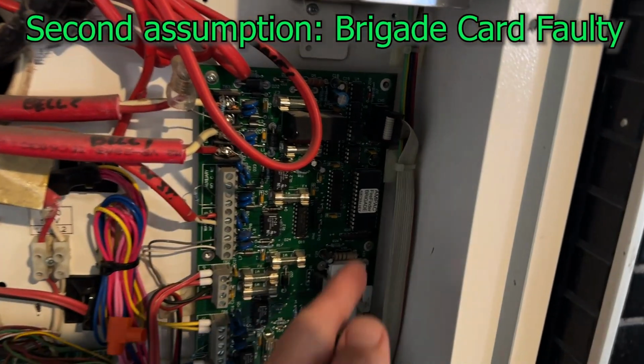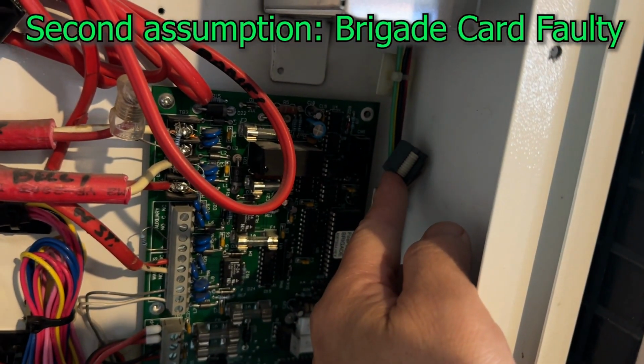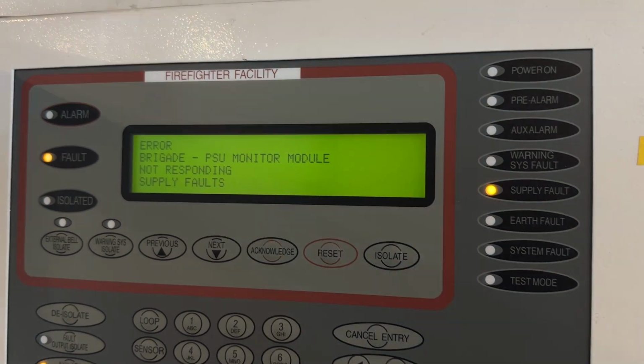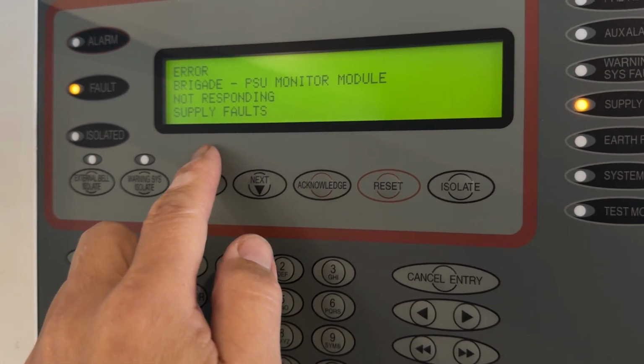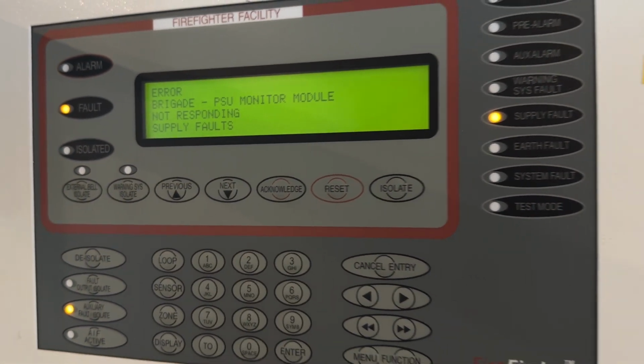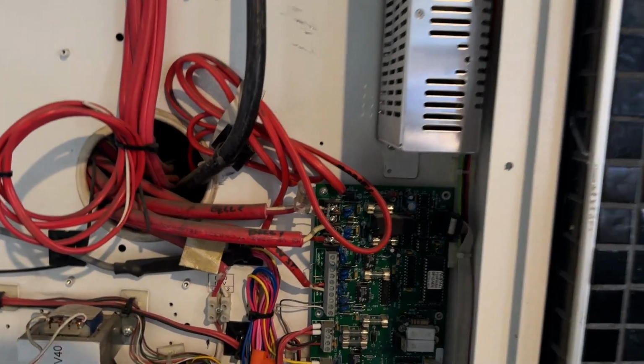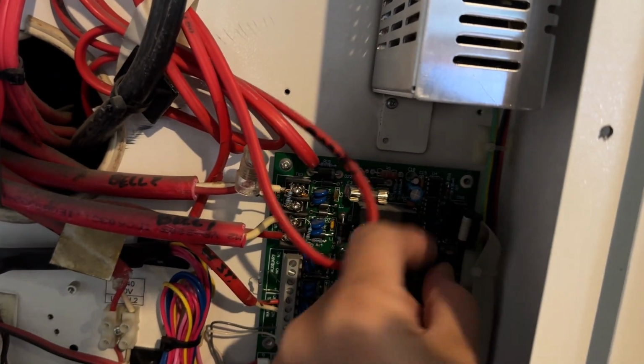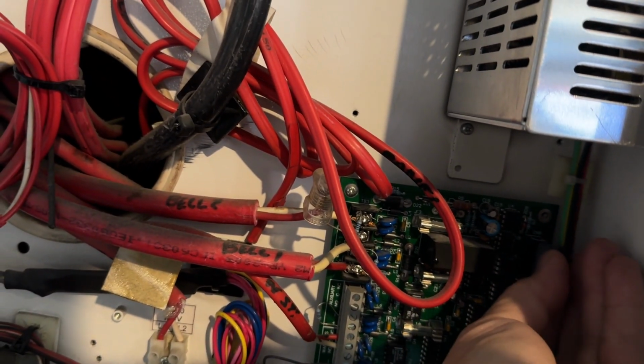Okay, temporarily I disconnect the power supply module monitoring. That goes here. And that's what you get: fire brigade power supply monitor module off. Now we're going to switch that thing back. Hopefully I can do it quick.